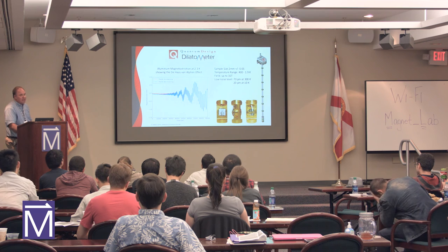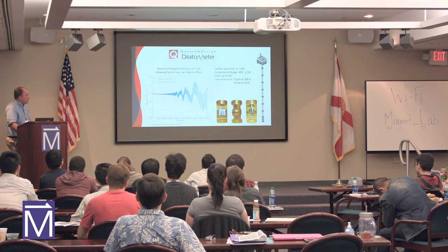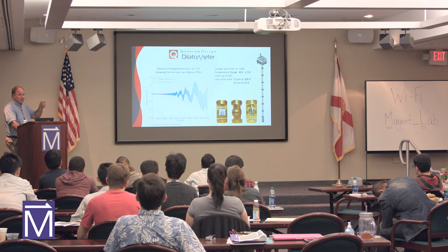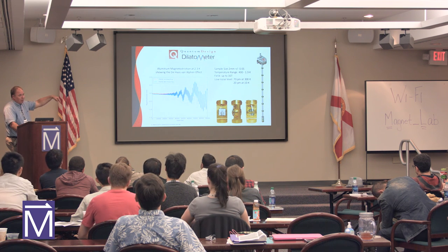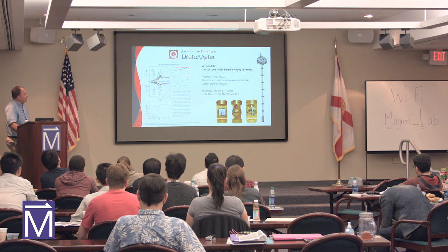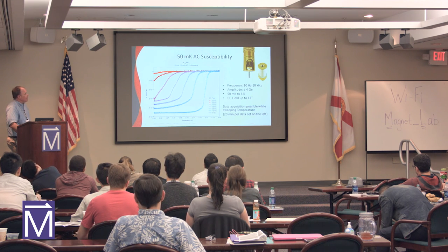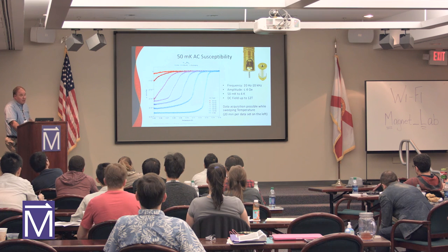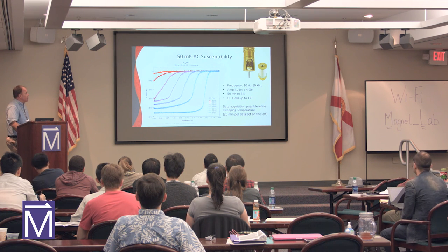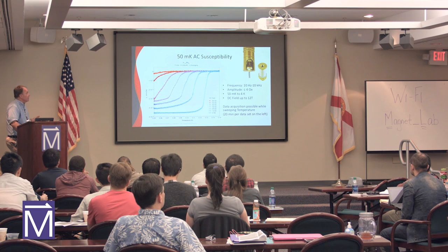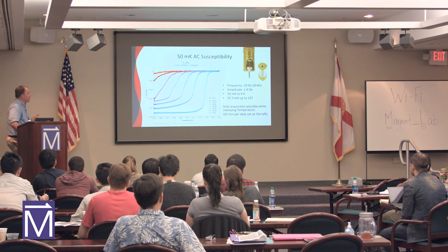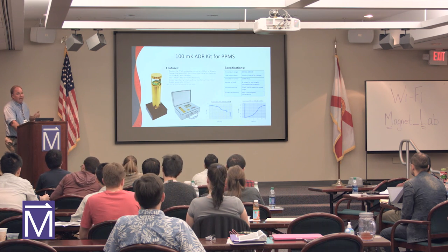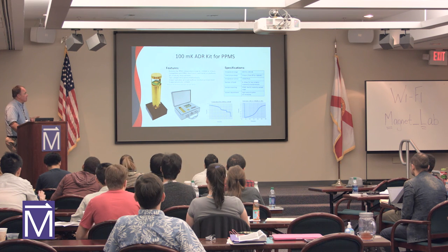What's new at QD? We developed a dilatometer, so you can do the de Haas-van Alphen effect with thermal expansion, a new probe that we put in the system to do these things. There are some nice papers on this, on a couple of compounds. We have an AC susceptometer for the Dilfridge, so you can do AC susceptibility at 50 millikelvin, not as low as you can do here, but you can add these samples into it. And we added an ADR module to the system, so you can do transport at 100 millikelvin.